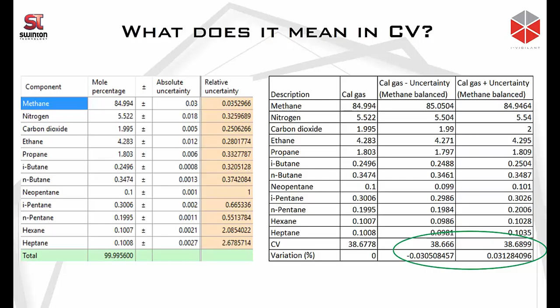However, if we order a cal gas that has 2% uncertainty on each individual component rather than a small uncertainty on each component, we will be subject to a possibility of CV that goes plus minus 0.22%. Now this is a problem because the calibration gas quality impacts the measurement directly, because our measurement will only be as good as our calibration gas to begin with. So with a 0.22% uncertainty, before we actually measure the process gas, we have an uncertainty that is quite high already. So our minimum uncertainty to begin with is 0.22%.